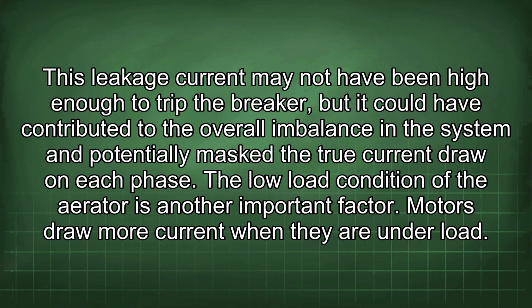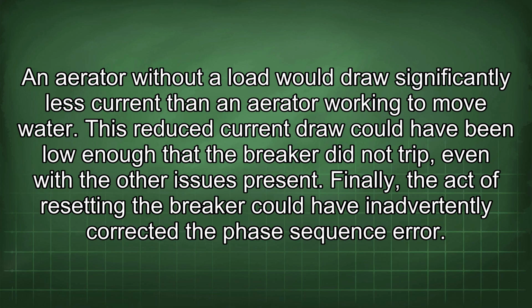The low load condition of the aerator is another important factor. Motors draw more current when they are under load. An aerator without a load would draw significantly less current than an aerator working to move water. This reduced current draw could have been low enough that the breaker did not trip, even with the other issues present. Finally, the act of resetting the breaker could have inadvertently corrected the phase sequence error.